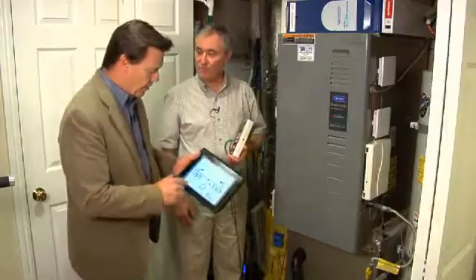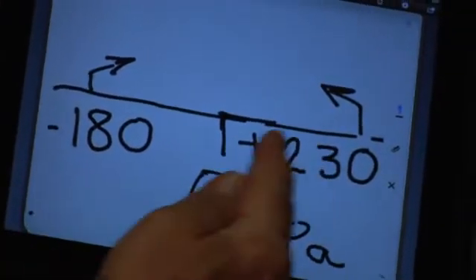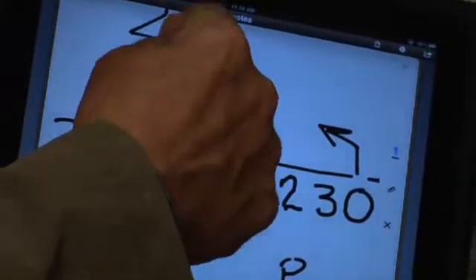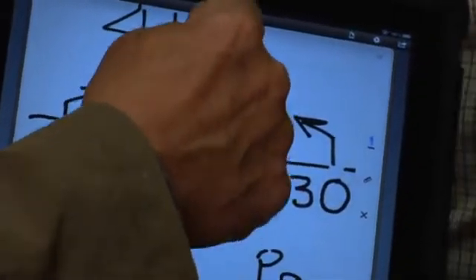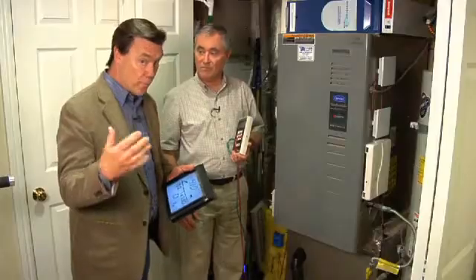If we look at this on a scale, we're going from minus 180 all the way to positive 230 — that's 410 pascals of pressure difference, which is way above the 125 pascals recommended by the manufacturer. That means we've got a lot of restrictions here that we have to figure out how to fix in order to get adequate air flow to provide cooling and efficiency.